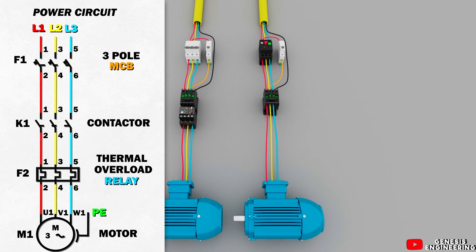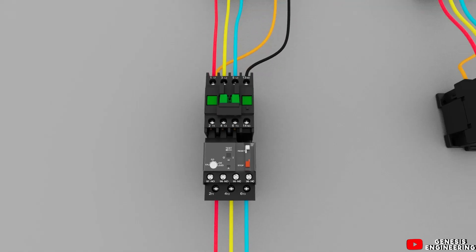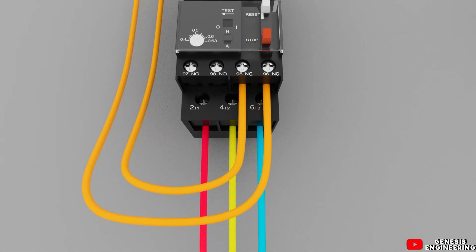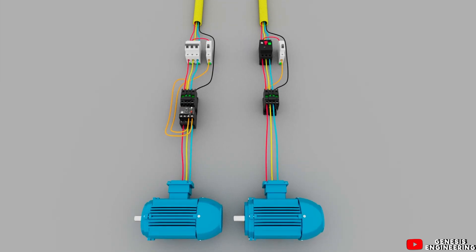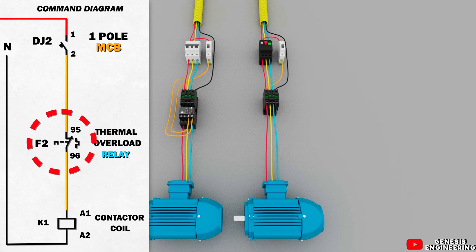The power contacts of the thermal relay are only connected to the contactor, so you must use the auxiliary contacts of the thermal relay to turn off the motor when there is an overload. We take one of the phases connecting to the contactor coil and connect it to the normally closed contact of the thermal relay — terminal 95 is the normally closed input and terminal 96 is the output. We connect this phase to 95 and leave from 96 to A1 of the contactor. Now in the command diagram we have the normally closed contact of the thermal relay in series with the contactor coil, and if there is an overload, this normally closed contact will open, interrupt the coil energy, and turn off the motor.